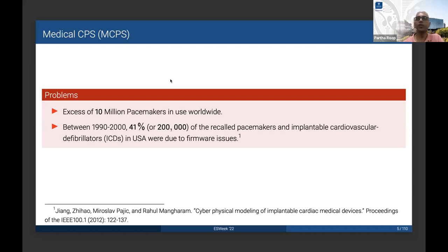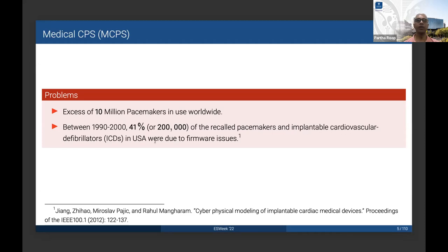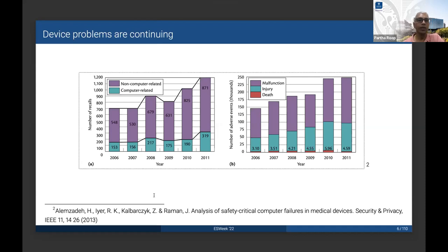When we talk about such medical CPS, obviously such devices are highly safety critical. They are usually certified by FDA. But many pacemakers had firmware-related issues and other kinds of safety-related issues. Between 1990 and 2000, 41% and roughly 200,000 of recalled pacemakers and implantable ICD devices in the USA had firmware issues. More recently, a 2013 publication talks about a huge number of recalls between 2006 to 2011, with adverse events including injury, malfunction, and death, and the numbers are staggering.